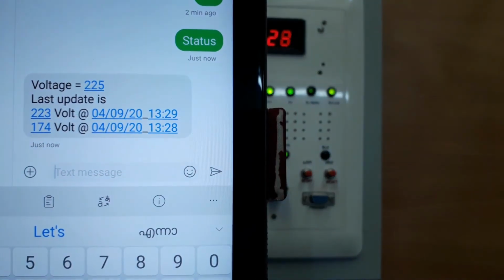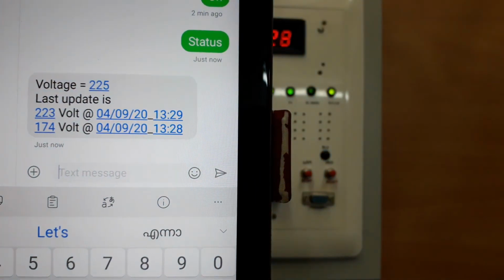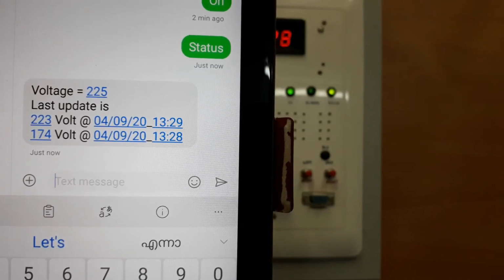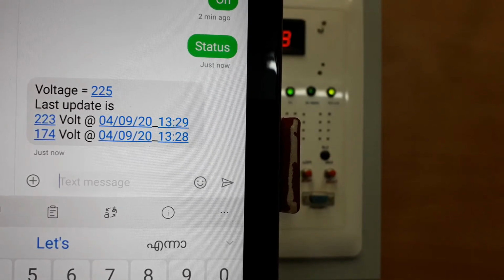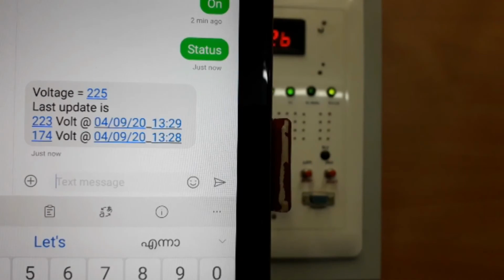It means the current voltage of our system is 225. In the fourth line we see 174 voltage at time 1328, meaning the system voltage went below the lower cutoff voltage at that time. In the third line we see 223 voltage at time 1329, indicating that the system recovered from the lower cutoff condition and returned to normal at that time.